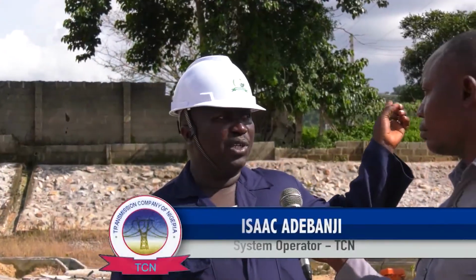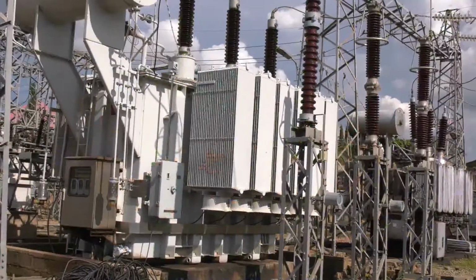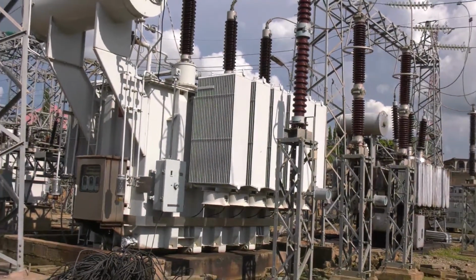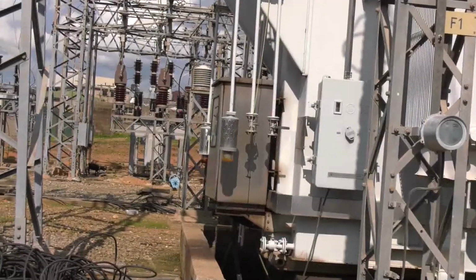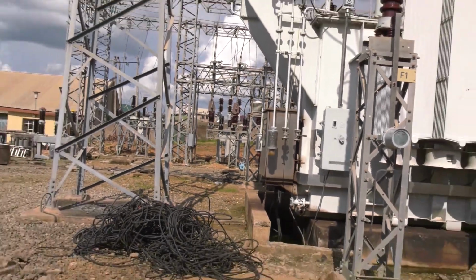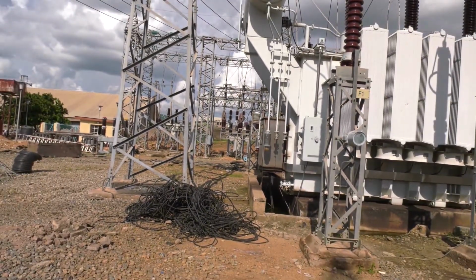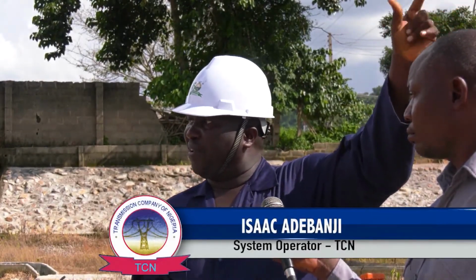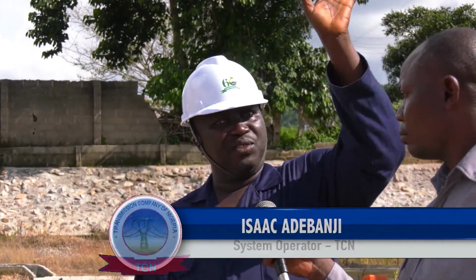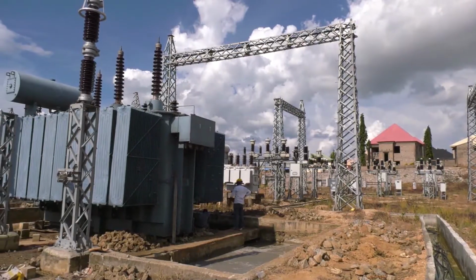We have two infeeds, one from Benin and the other from Ajaokuta, so that there will be room for flexibility. If there is a problem, we can open one of our isolators and feed from Ajaokuta. And if Ajaokuta is having a problem, we can still feed from Benin by opening the Q65, the isolator facing towards Ajaokuta, so that we'll be feeding from the Benin end.